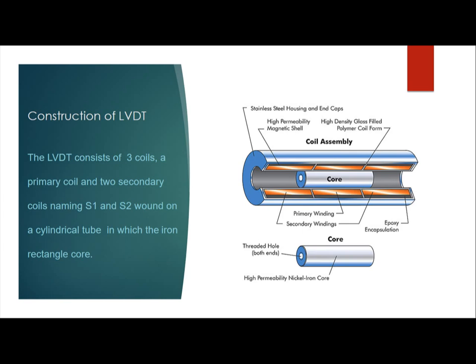In the construction of LVDT, as we talked about previously, V stands for variable, meaning a movable coil. We know that there is a coil inside the hollow tube. LVDT consists of three coils: a primary coil and two secondary coils, named S1 and S2. The voltage in S1 is EMF1 or E1, and the voltage in S2 is EMF2 or E2. There is a slender tube in which the iron core moves.